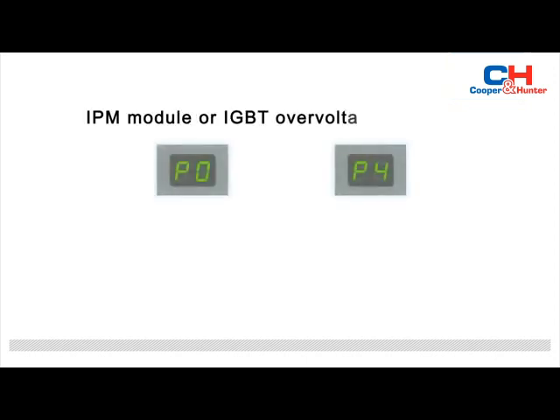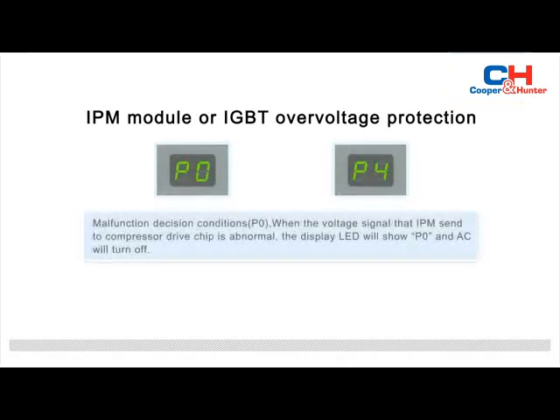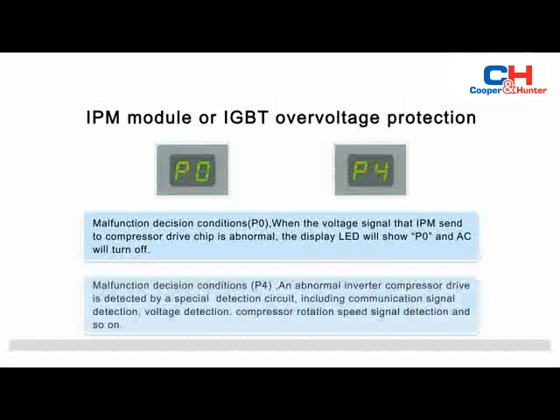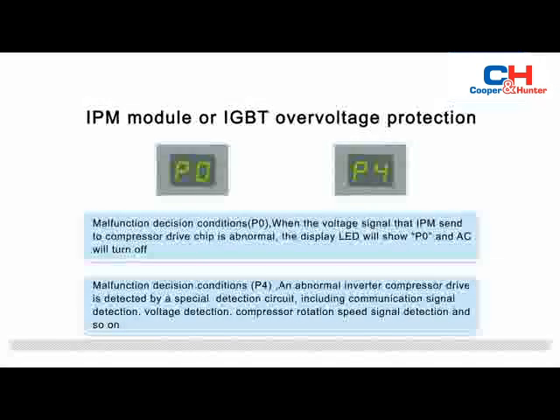When the indoor unit displays P0 or P4, that indicates an IPM module fault or IGBT overvoltage protection.